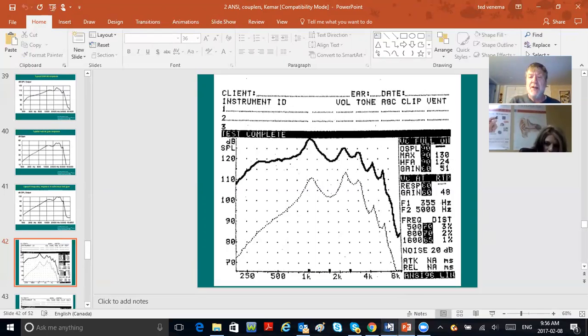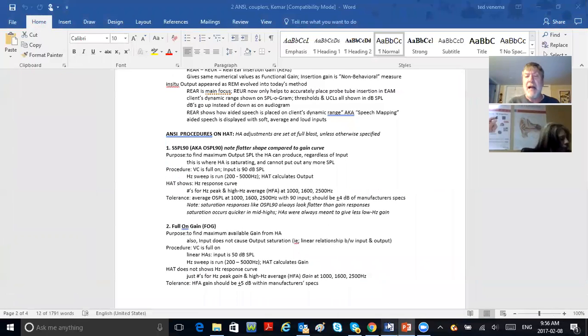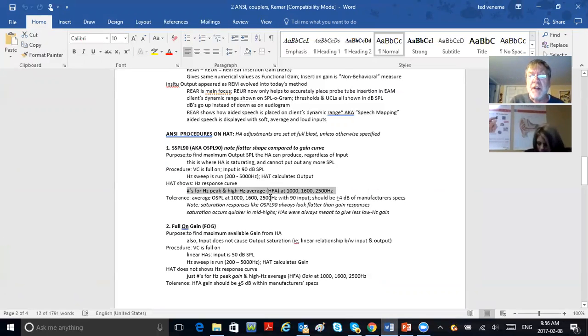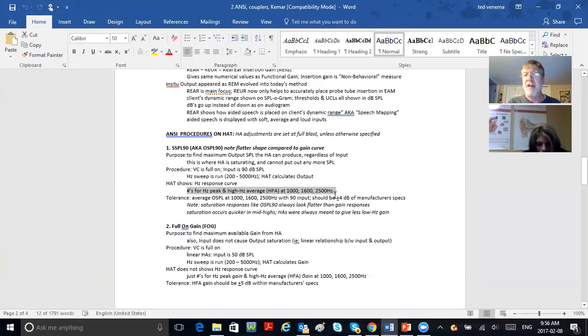The tolerance: the average OSPL 90 at 1000, 1600, and 2500 Hz with a 90 dB input should be within plus or minus 4 dB of manufacturer specs.